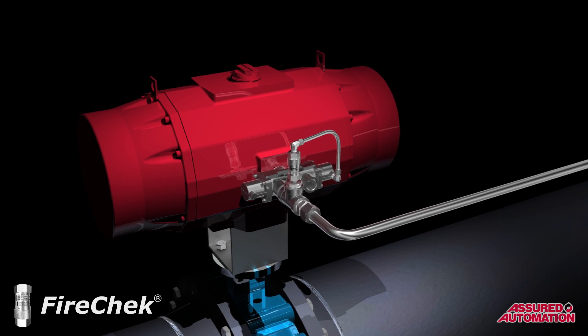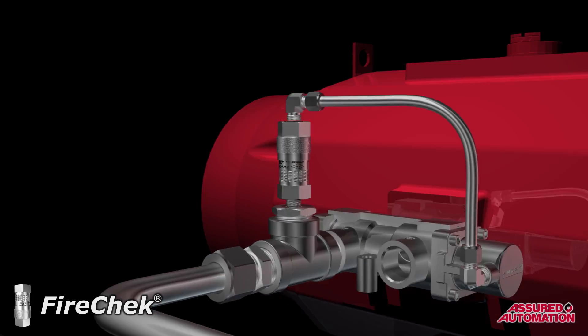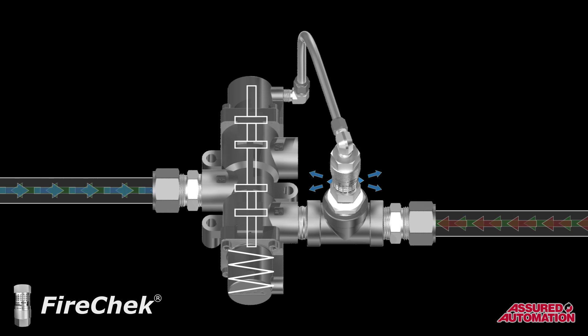In cases where the actuators are large enough to require a high-flow piloted spool valve for operation, the FireChek valve is installed on the external pilot line of the spool valve. This setup provides the same functionality, but does so in a slightly different manner. The FireChek valve vents the spool valve's pilot, causing the spool valve to shift, which then exhausts the actuator.